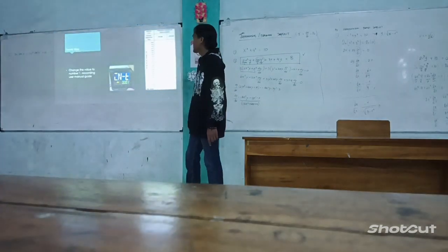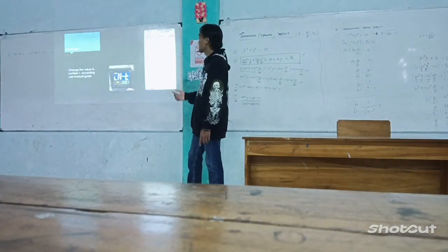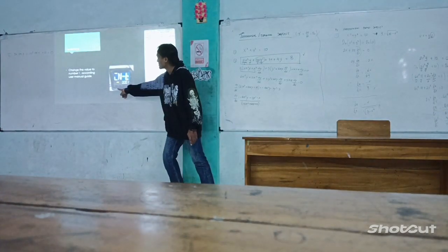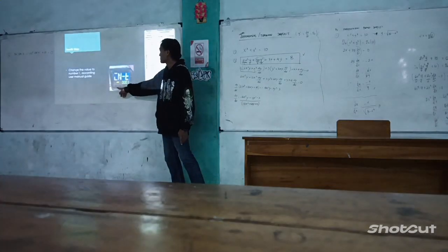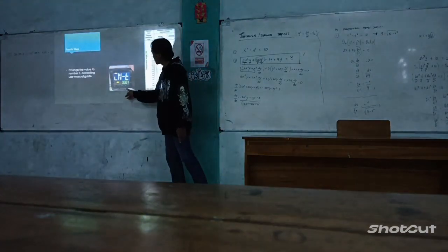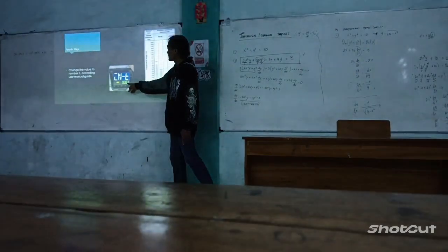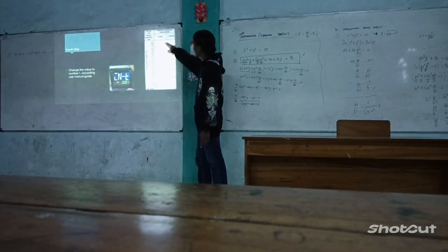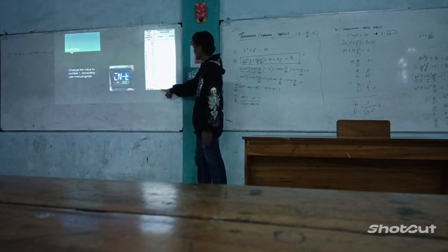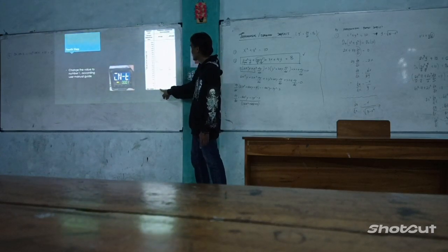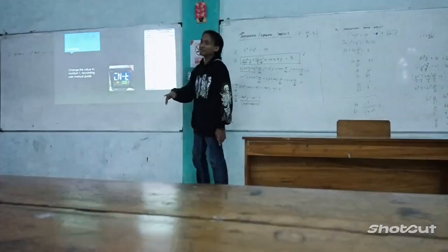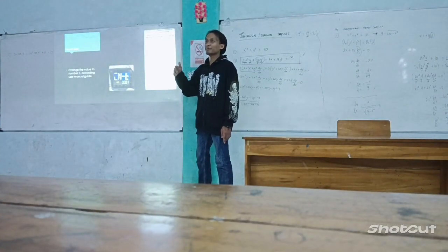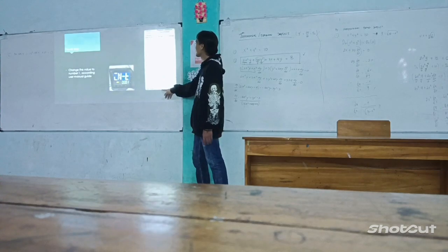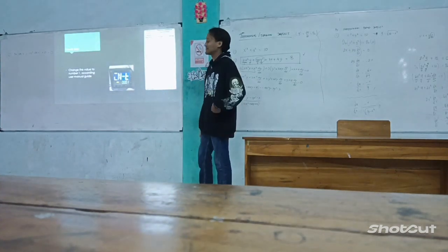The fourth step, change the value to number 1 according to the user manual. After pressing this button, it will show this picture and you change this to number 1. Number 1 is PT100. There are a lot of values, but I will show only the PT100. And number 0, if you're using a PT1000, has a bigger capacity than PT100. Next.